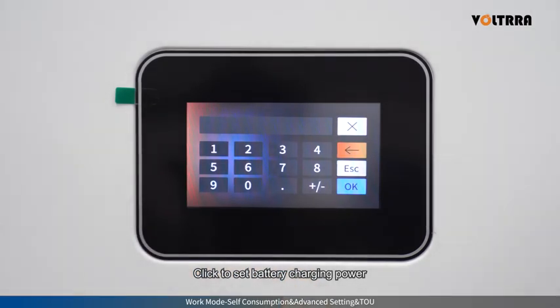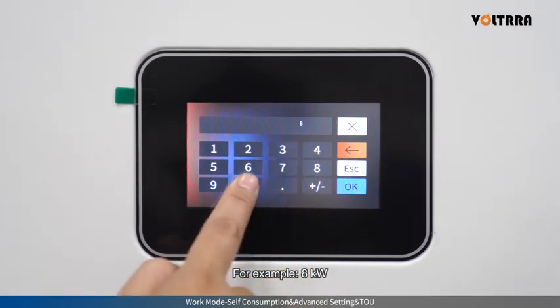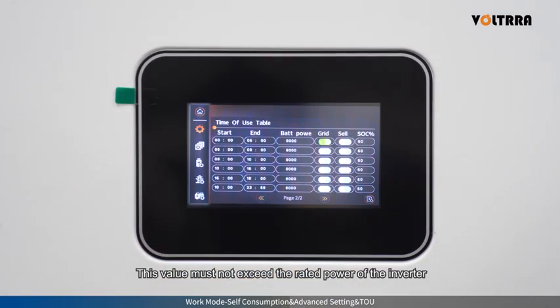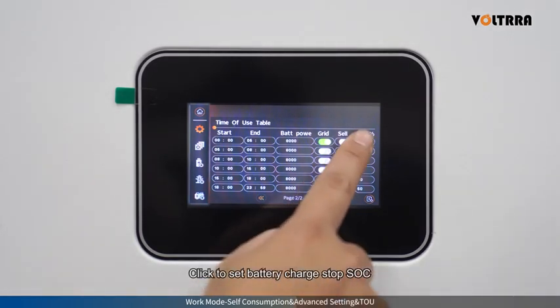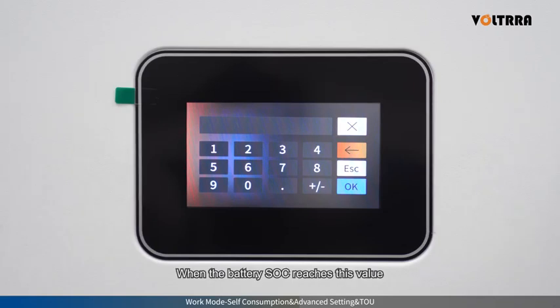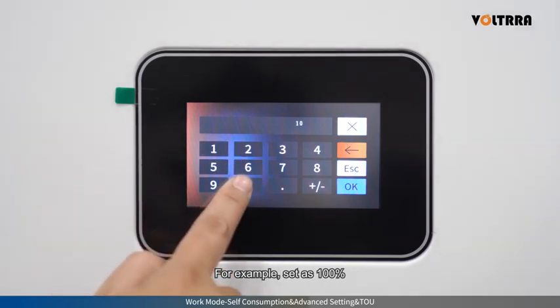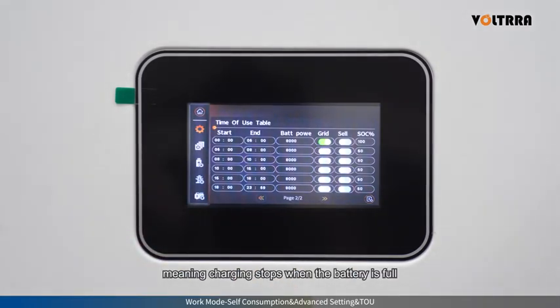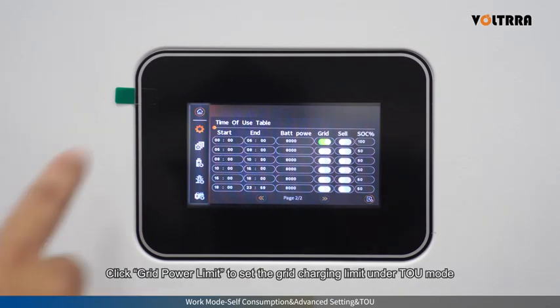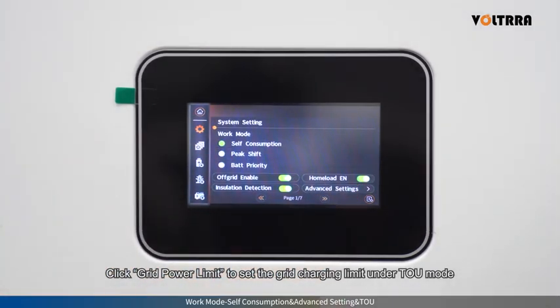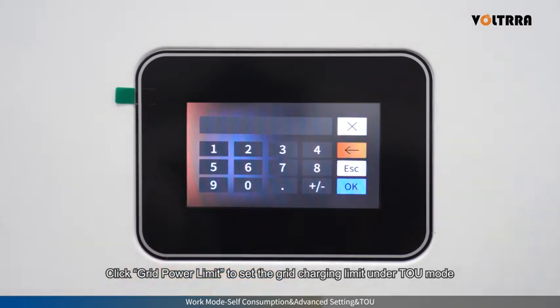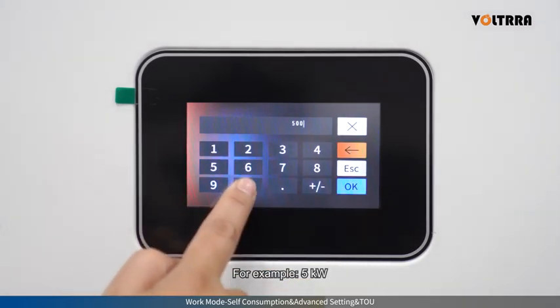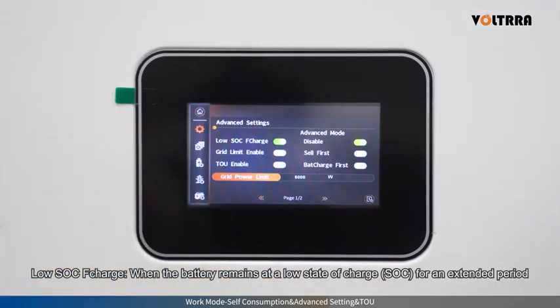Click to set battery charging power. For example, 8 kilowatts. This value must not exceed the rated power of the inverter. Click to set battery charge stop SOC. When the battery SOC reaches this value, charging stops. For example, set as 100%, meaning charging stops when the battery is full. Click Grid Power Limit to set the grid charging limit under TOU mode. For example, 5 kilowatts.